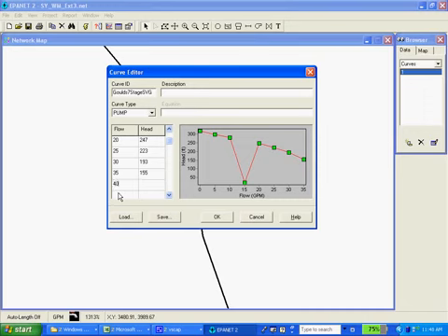My last point here is 40. My booster station is a very small booster station, and a pretty small pump in there. See there, we've got an error somewhere. Obviously somewhere at the 15 mark, we've entered a strange number, so we're getting this dip in the curve. It's kind of nice to have this graph to be able to see that, otherwise you might miss it. You see here under 15, I entered 20 instead of what it should have been, which is actually 265. Entering that corrects it, and we get something that looks very much like the manufacturer's pump curve here.